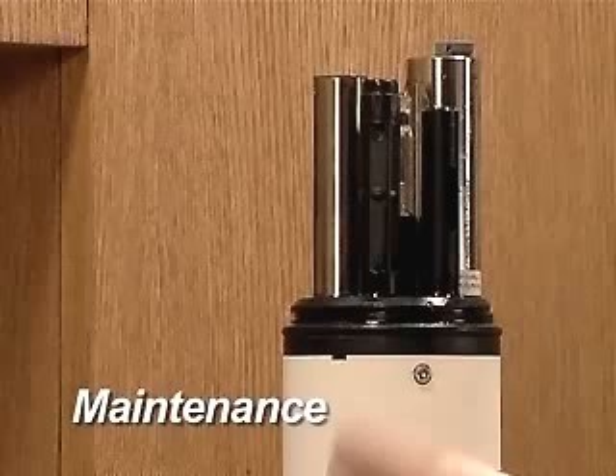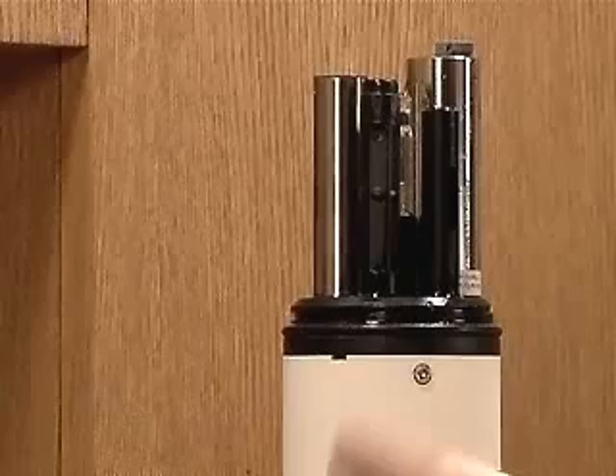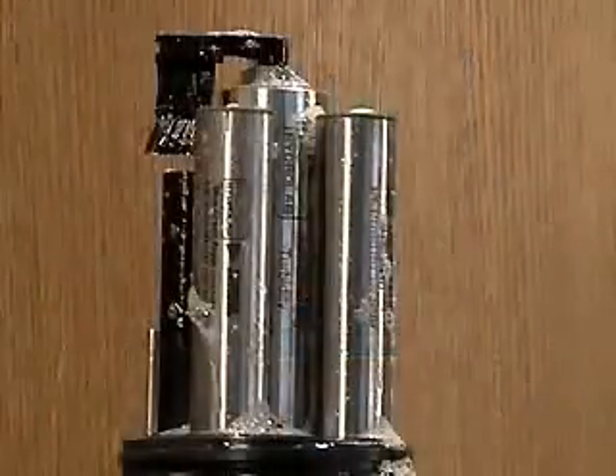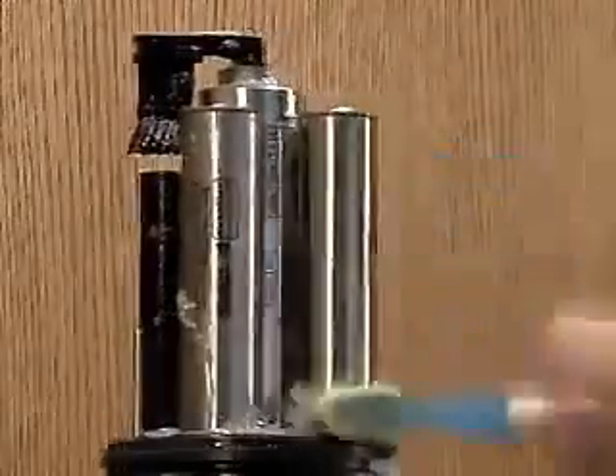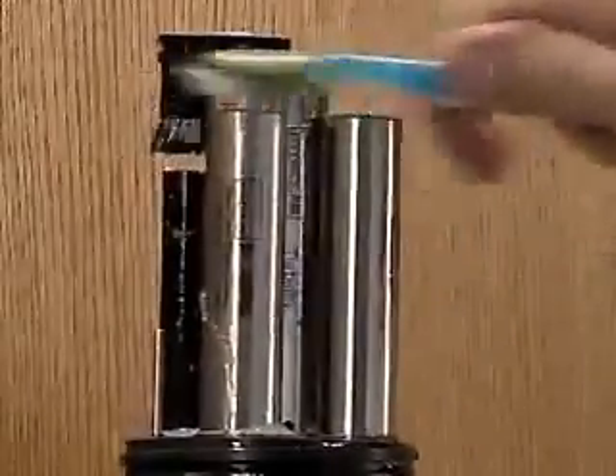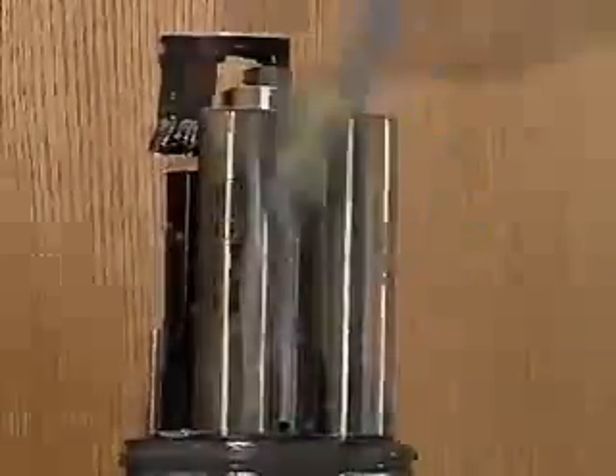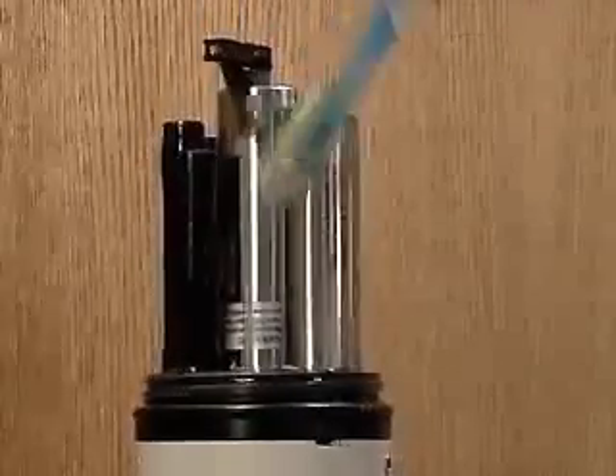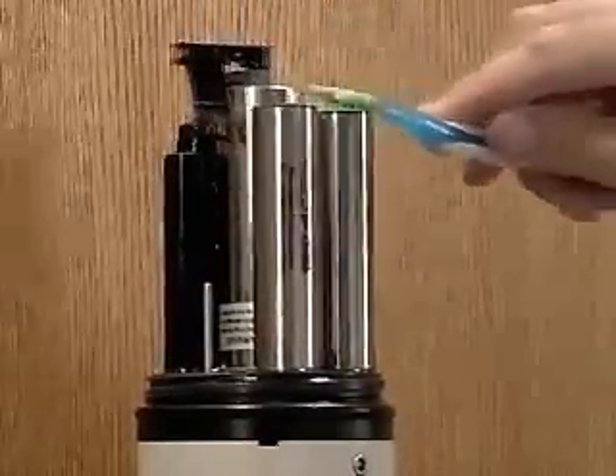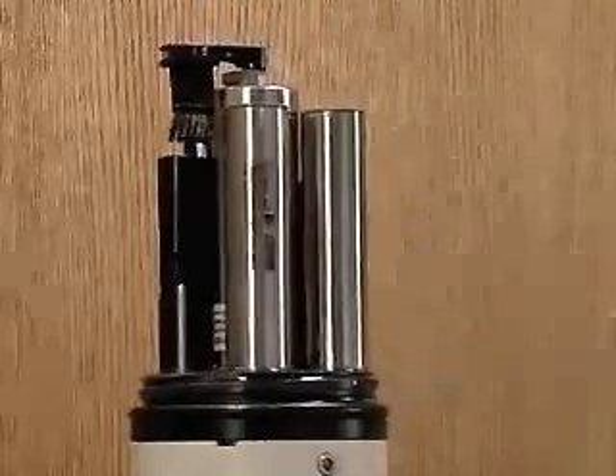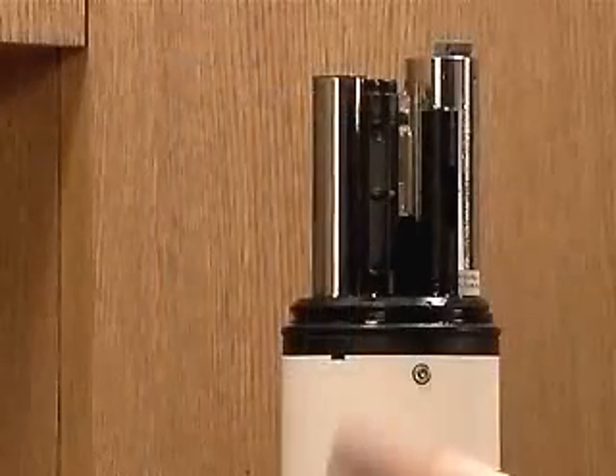Maintenance. The Hach LDO probe is nearly maintenance-free. To ensure accurate readings and a long sensor life, the probe should be kept clean. After each deployment, the sensor should be cleaned with a cotton swab or soft brush and soapy water to remove any oils or organisms. Organisms living on the sensor will consume or produce oxygen and change the readings.